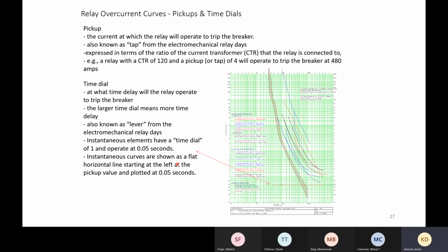An important thing to note, and I think I commented some in the chat about this, is you can't coordinate instantaneous elements. By definition, an instantaneous element is an element that operates with no intended time delay. If we look here, this number and this number are pointing to two different pickups, but the lines lay right on top of one another. So if I have a 3000 amp fault, I come in contact with both lines at the exact same time. So there's no coordination between them. You really can't coordinate instantaneous elements.